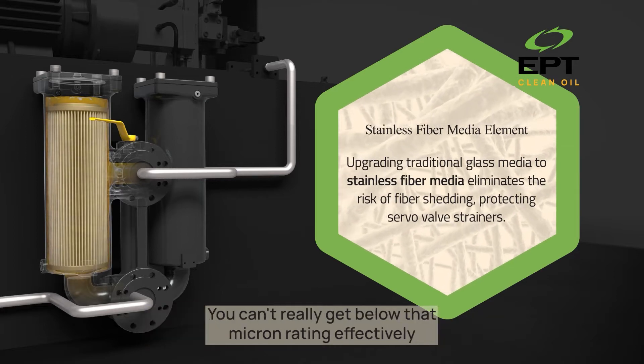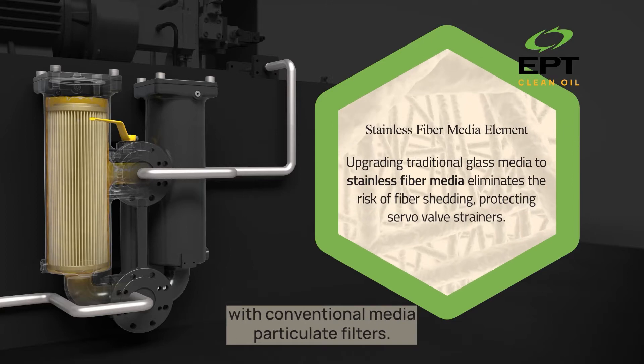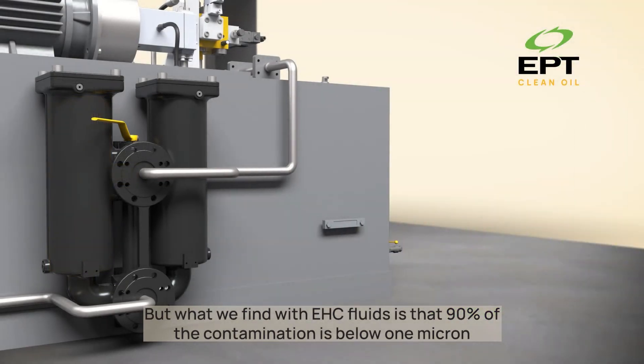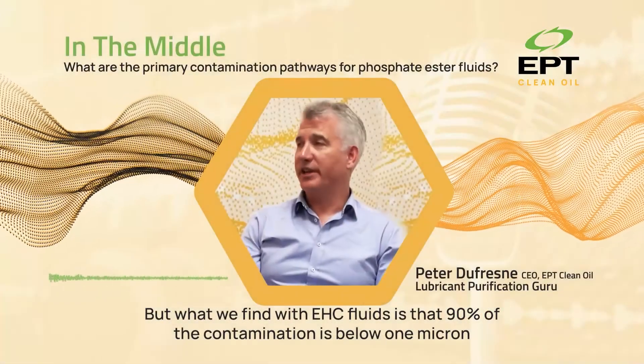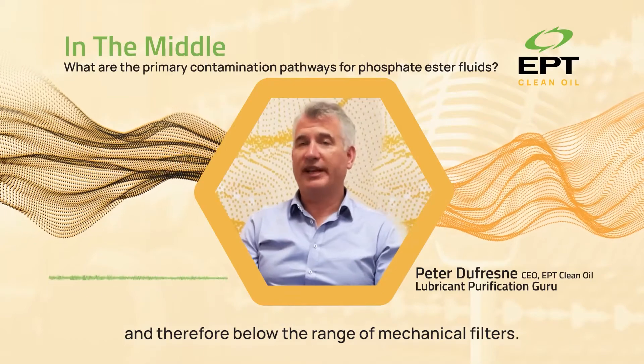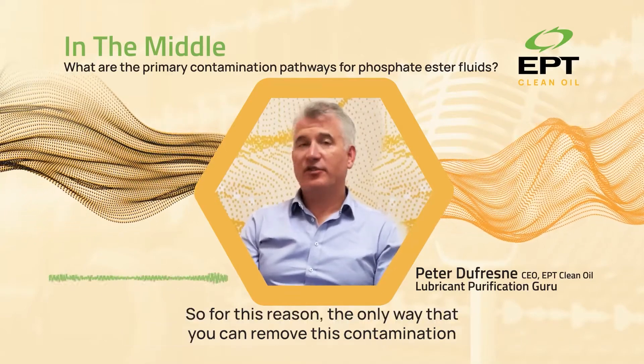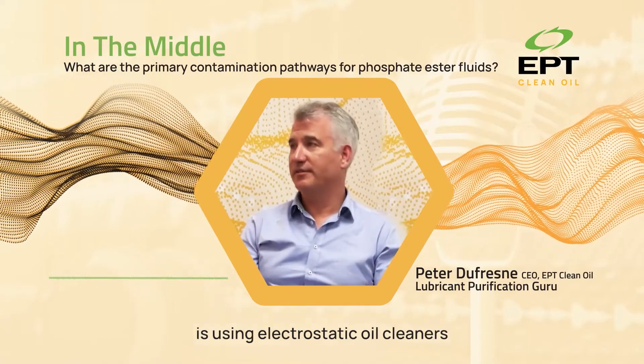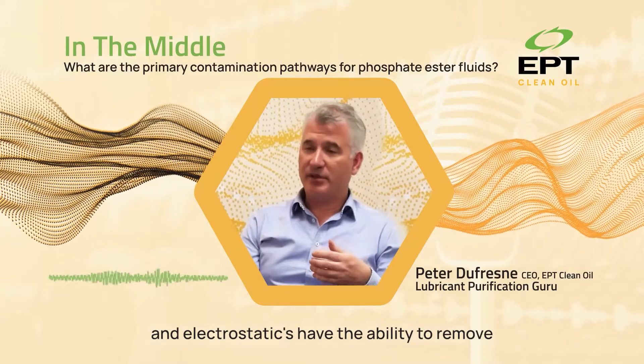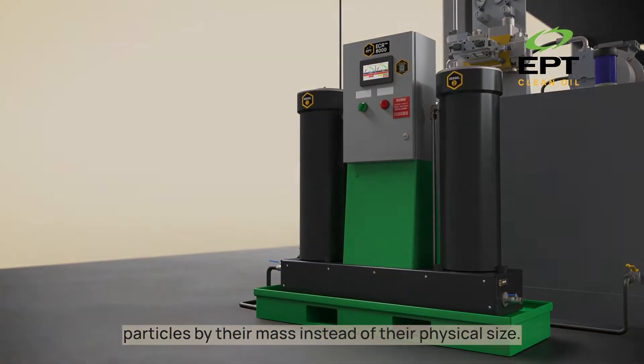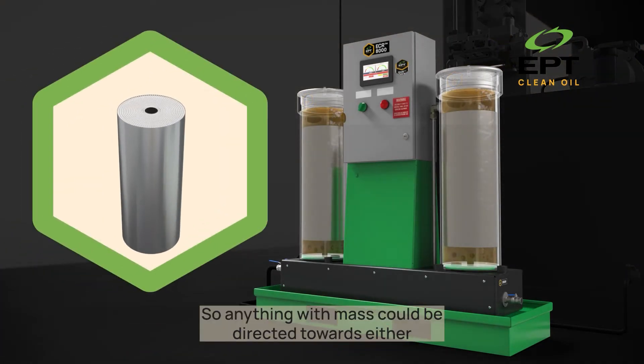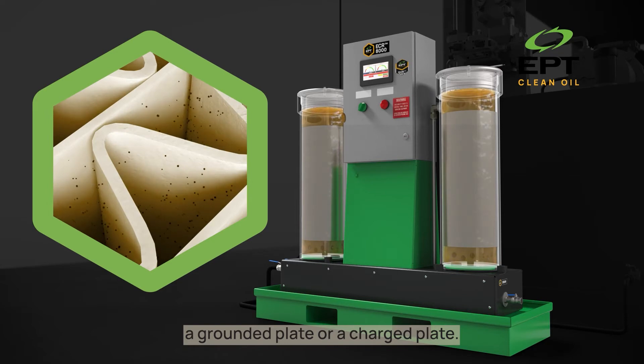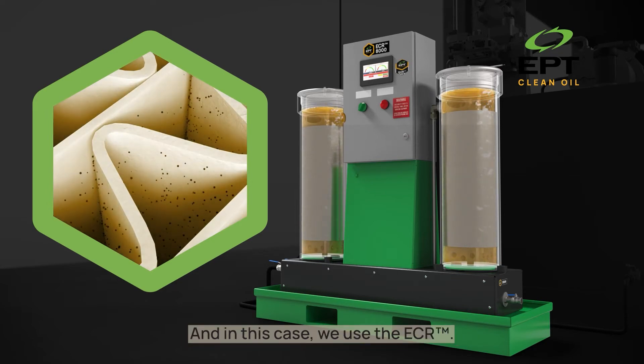You can't really get below that micron rating effectively with conventional media particulate filters. What we find in EHC fluids is that 90% of the contamination is below 1 micron and therefore below the range of mechanical filters. For this reason, the only way to remove this contamination is using electrostatic oil cleaners. Electrostatics have the ability to remove particles by their mass instead of their physical size, so anything with mass can be directed towards either a grounded plate or a charged plate. In this case, we use the ECR.